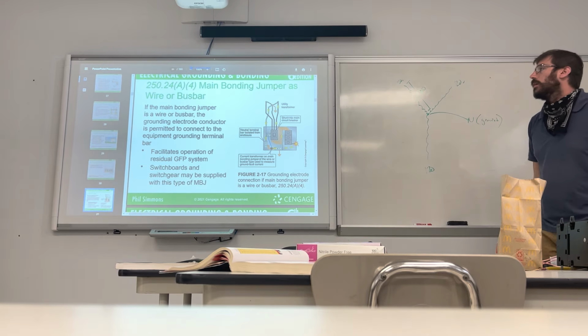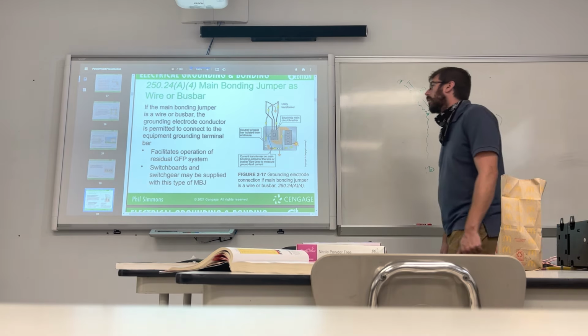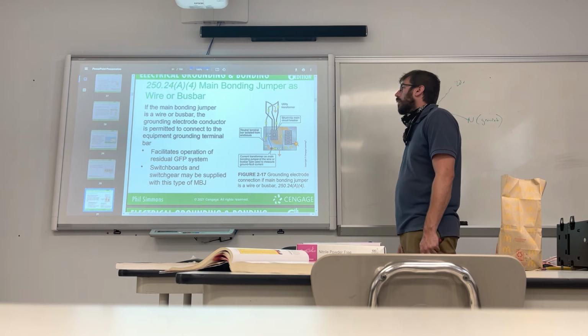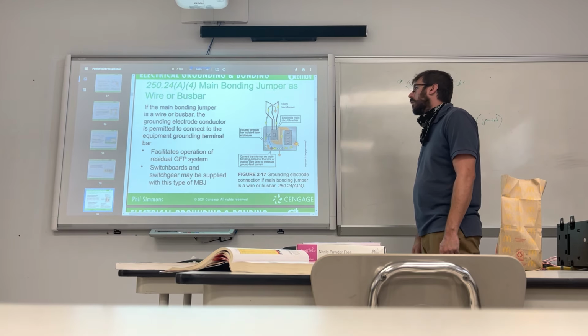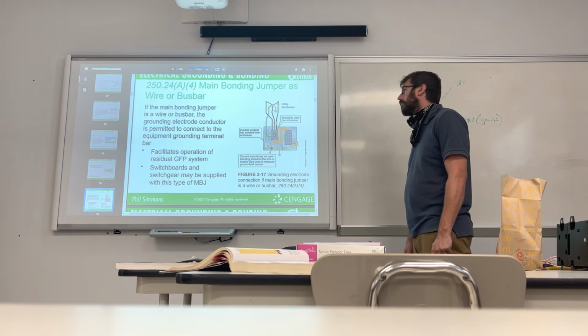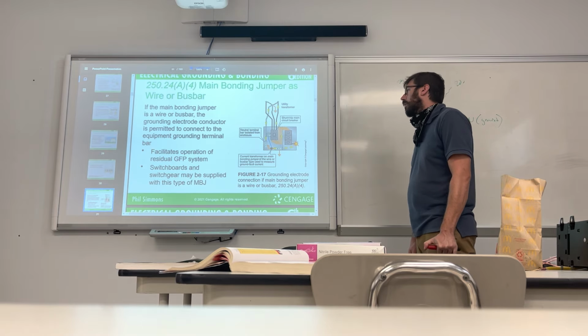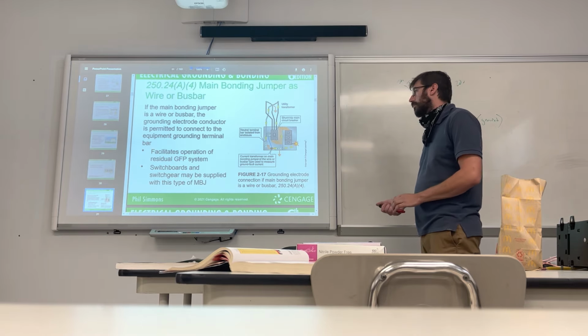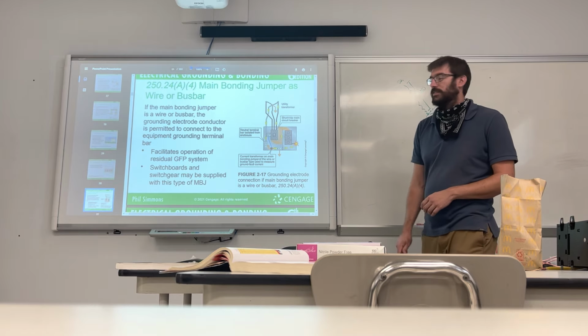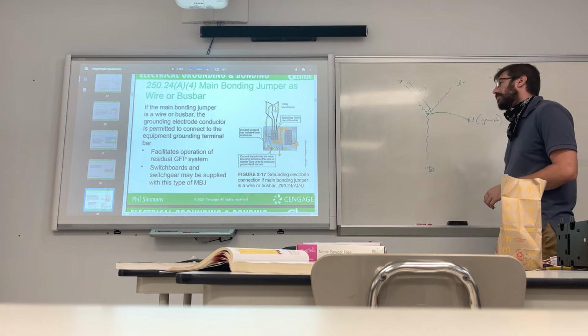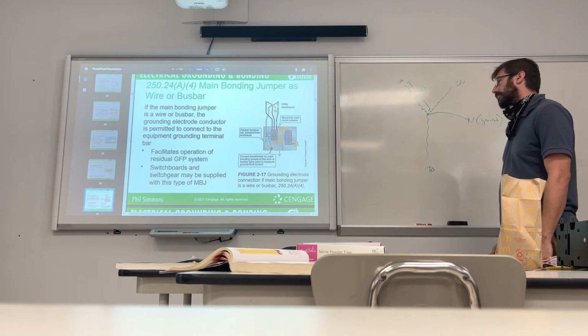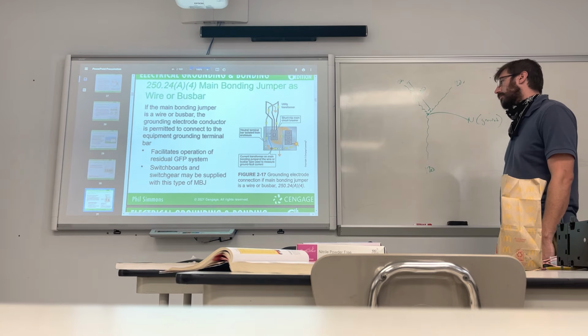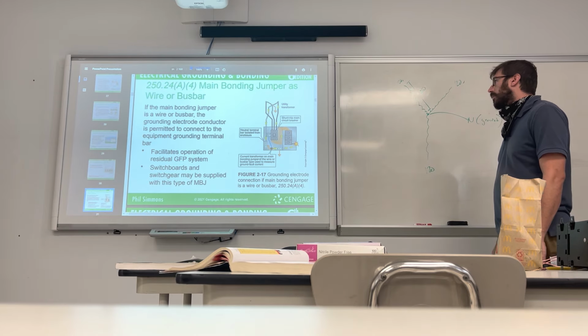Main bonding jumper is wire or bus bar. If the main bonding jumper is a wire or bus bar, the grounding electrode conductor is permitted to connect to the equipment grounding terminal bar. Facilitates operation of residual GFP system. Switchboards and switchgear may be supplied with this type of MBJ.